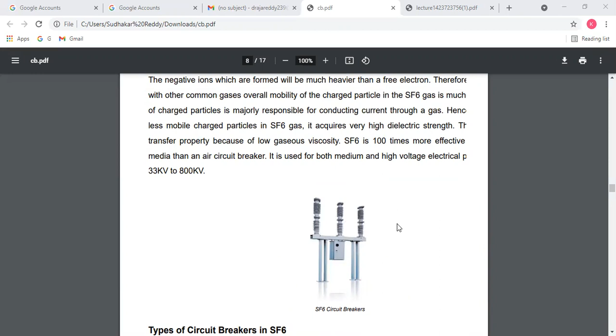Now, according to classification of voltage levels, SF6 circuit breakers are mainly classified into three types. First one is the single interrupter SF6 circuit breaker, applied up to 220 kV. This type is used especially near transformers, distribution transformers. Next, the two interrupter SF6 circuit breaker, applied up to 400 kV. This is also used near substations, domestic substations.